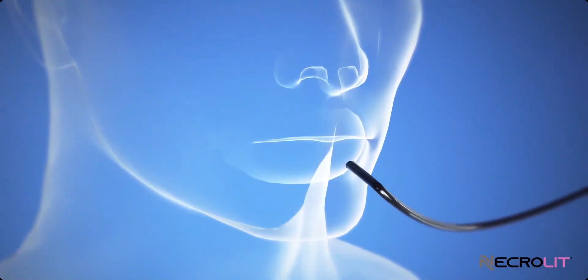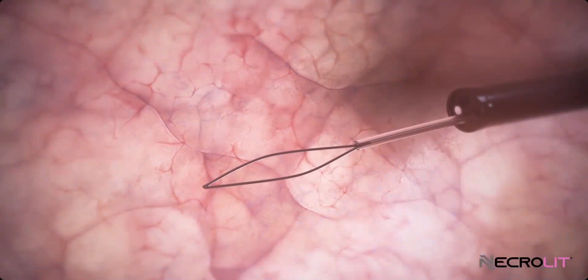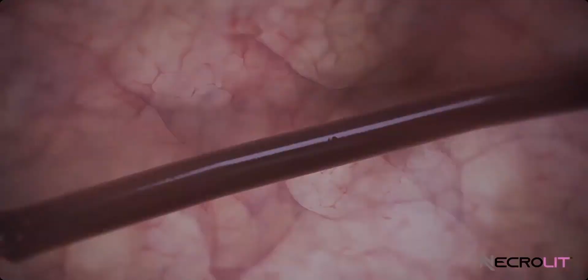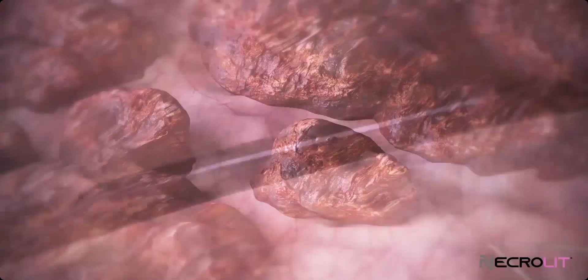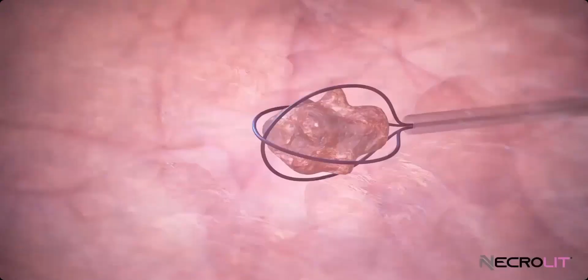The transluminal procedure is performed by using a flexible gastroscope with a water irrigation system and CO2 insufflation inserted through the fistula tract or lumen-opposing metal stents. Tissue debris is mechanically fragmented and removed alternatively using the two devices inside the double lumen catheter. The monofilament loop cuts and grips the necrotized tissue, and the basket retrieves the tissue. The entire procedure is performed with NecroLit without the need for accessory exchange, saving costs and time of the necrosectomy procedure. NecroLit is a new, unique device dedicated to direct endoscopic necrosectomy that permits simultaneous resection and retrieval of the necrotic tissue.